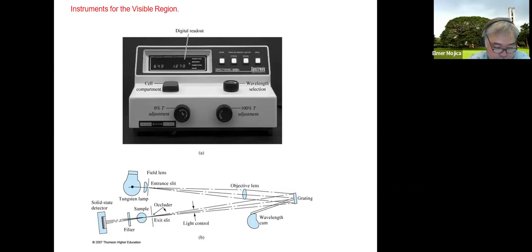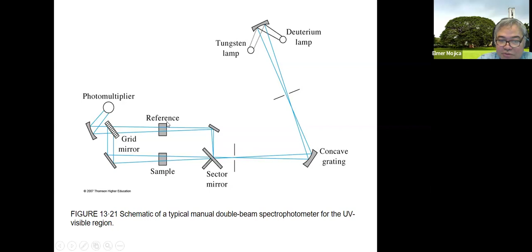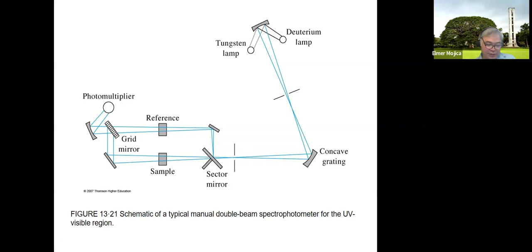Now, if you have a typical manual double beam spectrophotometer for a UV visible region, so this is what you have, the light sources, and then it passes through, okay, a slit, there's a concave grating there, okay, then pass to another slit. So there's a mirror that will split the light to go to the reference and the sample, and then it will be going at the same time to the detector, which is a photomultiplier. Now, if you have this Varian Cary, that's one of the instruments that we have in the lab. So this is how it looks like. The principle is still the same.